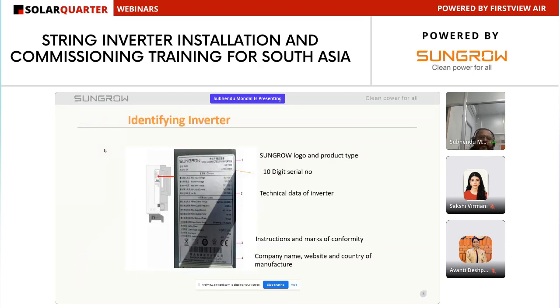Here is the inverter logo and inverter sticker. You can find it on every inverter. First it's the product logo. Next we can find the inverter's 10 digit serial number. Next the technical data of the inverter, like what is the MPPT volt, what is the AC volt, and what is the current rating, MPPT current rating. You can find all this basic data from this sticker also. Next, instruction marks of conformity. Then at the bottom of this sticker you can find company name, website, country of manufacture.